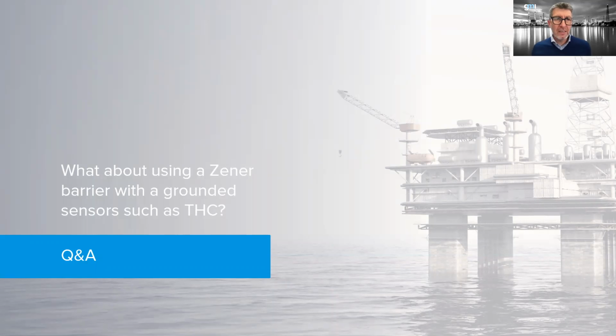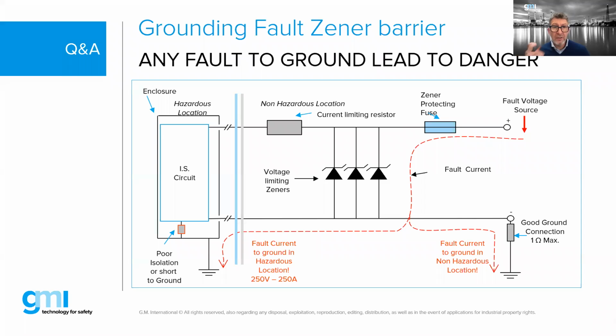What about using a Zener barrier with a grounded sensor? This is another issue. I don't know if we discussed this earlier, but there is another limitation when using a Zener barrier, which is the grounded sensor. You cannot use a Zener barrier with a grounded sensor because you would have two ground paths, as shown in this slide. We talked about this a little bit earlier. Because then a leg of the fault can go down one of the two legs, and you will not have control over it.